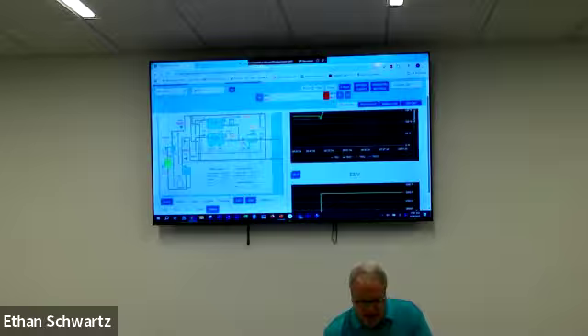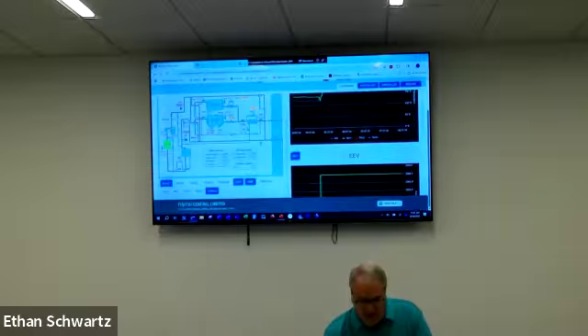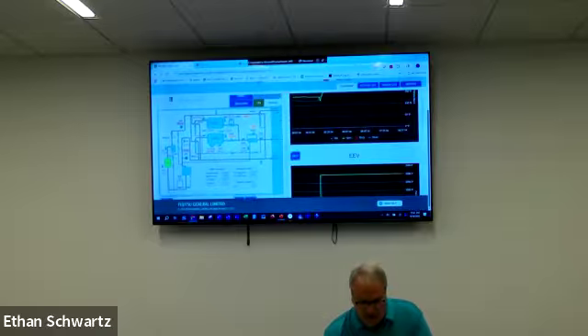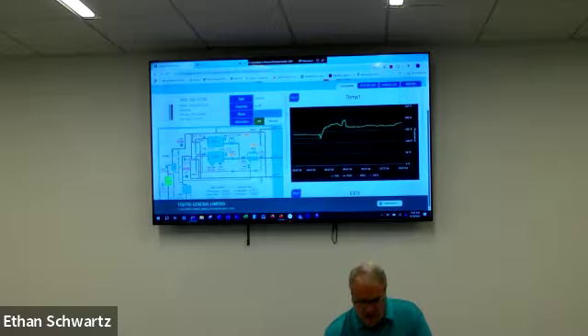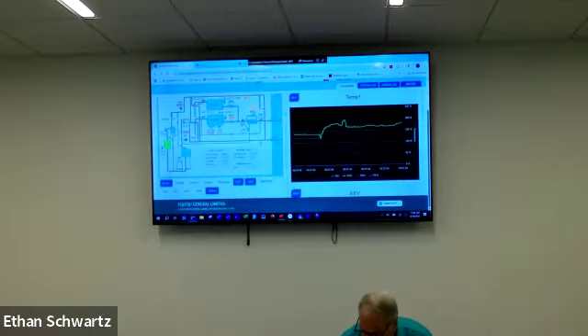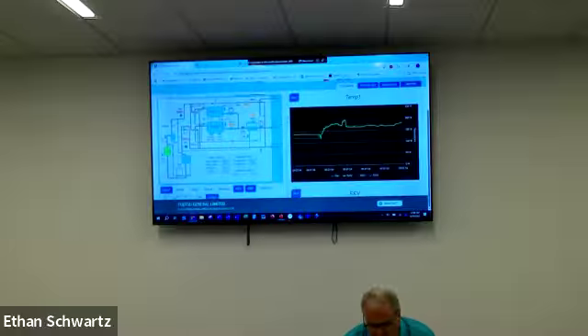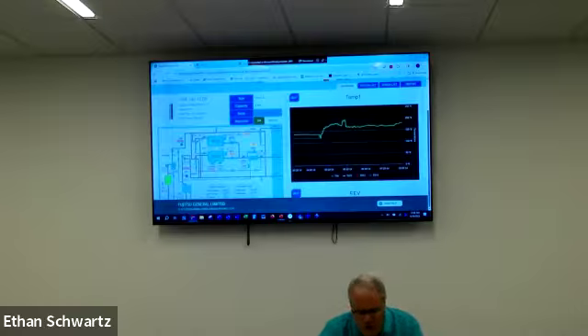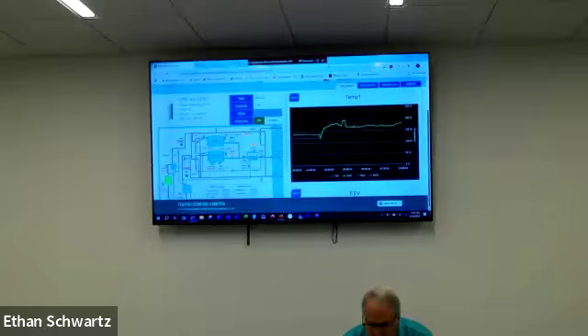The other thing is that it makes that building sticky to that contractor for preventive maintenance and keeps them from having to scramble a vehicle and a tech in order to figure out what's going on with the system. It might be something very simple. And I think it's just come out or will be coming out where we will be able to do the F340 hard resets directly through the cloud. So if it did trip off on high head pressure, then we'd be able to reset that remotely, or the contractor would be able to reset that remotely and see, was that just a one-off event because something happened, or do we really have an issue with the system. So I just wanted you to see that.